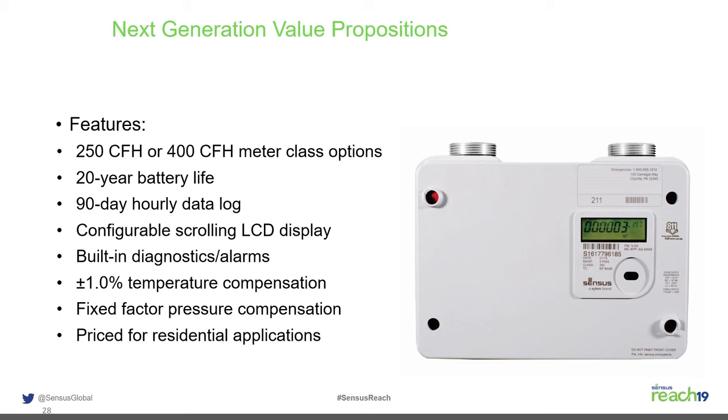Another advantage of the electronic platform is plus or minus 1% temperature correction. Bimetallic elements in diaphragm meters are typically plus or minus 2%, and only within minus 20 to plus 120 Fahrenheit. The SonixIQ achieves plus or minus 1% from minus 30 to plus 130 Fahrenheit, picking up roughly 1% more accuracy at colder temperatures — exactly when more gas is being used.